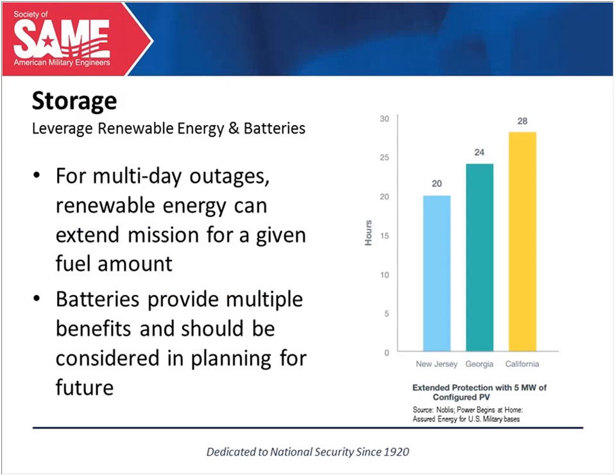One last thing on storage: renewable energy, you could call it the new form of storage. It's not going to take the place of fuel, at least not yet, and it's not going to take the place of most generation, because we're talking about PV or wind. You can't always assume that at any given instance you're going to have a lot of output from renewables, because the wind might not be blowing or it might be night. However, over the course of a multi-day outage, you can be pretty sure you're going to be producing energy from these systems, and that's going to take the load off your generators and save you fuel. That could be used to reduce the first cost of your fuel storage, but more typically it just gives you longer runtime. You get all the other benefits of renewable energy, but you also can extend your mission.